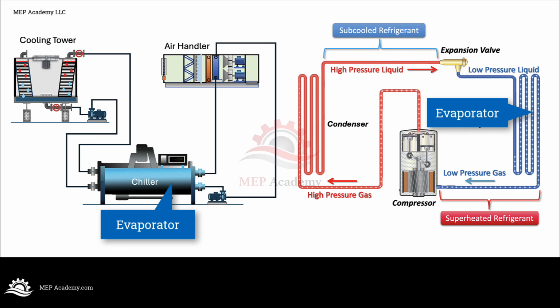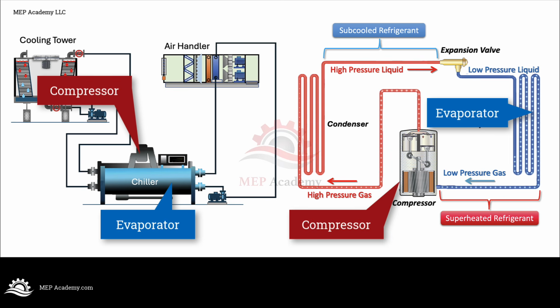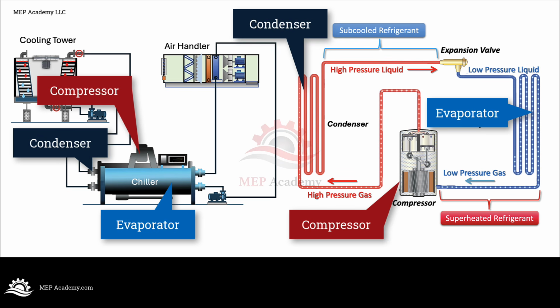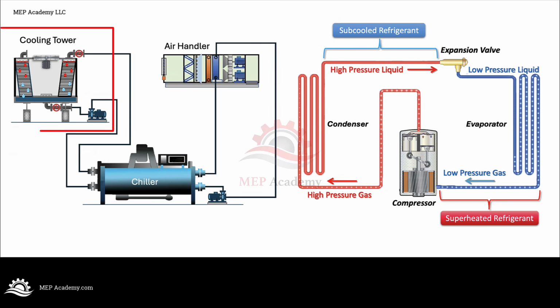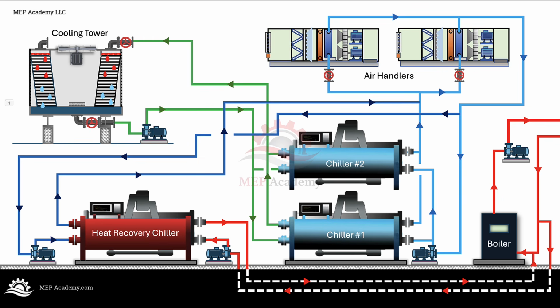Inside the evaporator, refrigerant absorbs that heat from the chilled water. The compressor then raises the pressure and temperature of the refrigerant. The hot refrigerant moves to the condenser, where the heat is transferred into the condenser water loop. The condenser water carries that heat to the cooling tower, and the cooling tower rejects it outdoors. So in a normal system, the path is simple. Heat comes out of the building. The chiller moves the heat into the condenser water. The cooling tower rejects the heat to the atmosphere. That works, but it also means the heat is wasted. A heat recovery chiller uses the same basic refrigeration cycle, but the application is different.